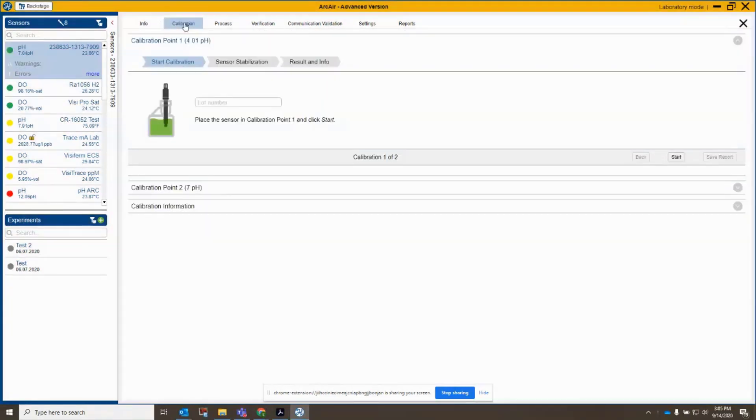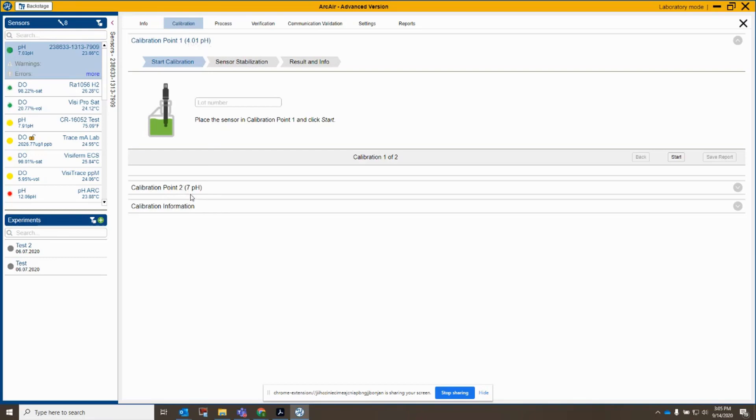So the first thing I notice when I go to calibration is I see that I have a calibration point 1, 4.01, and calibration point 2, 7 pH. So since my sensor is sitting in 7 buffer, let's see if we start there what happens. So I'm going to punch in just a mock lot number here, and let's start here.